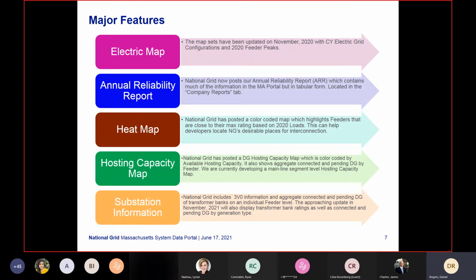The current substation information we have provides 3V0 information, which is your transformer high side protection, so that will give a substation restriction for DG. We also display aggregate connected and pending DG, which will usually trigger an ASO study in certain areas, so you can tell in a certain area how much connected and pending DG is based on the substation level information.